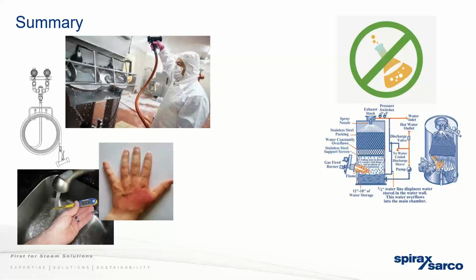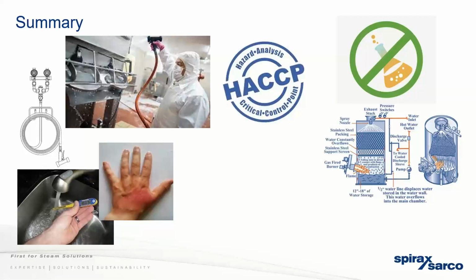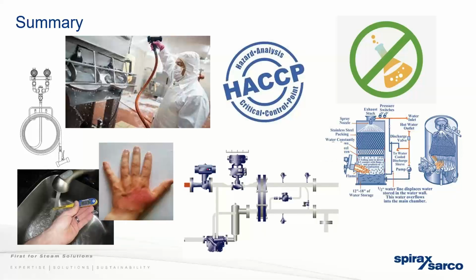Yeah, other direct fired type heaters could affect taste and flavor and deem the water not potable, so they are not recommended for wash down. And it would be a hazard, and that's where HACCP will come in. You want to identify those hazards and your critical control points. And discuss the heat exchangers with multiple safety levels and indirect heating to separate the potable water from the plant steam.